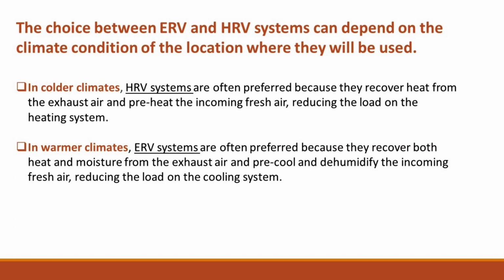The choice between ERV and HRV systems can depend on the climate condition of the location where they will be used. In colder climates, HRV systems are often preferred because they recover heat from the exhaust air and preheat the incoming fresh air, reducing the load on the heating system. In warmer climates, ERV systems are often preferred because they recover both heat and moisture from the exhaust air and pre-cool and dehumidify the incoming fresh air, reducing the load on the cooling system.